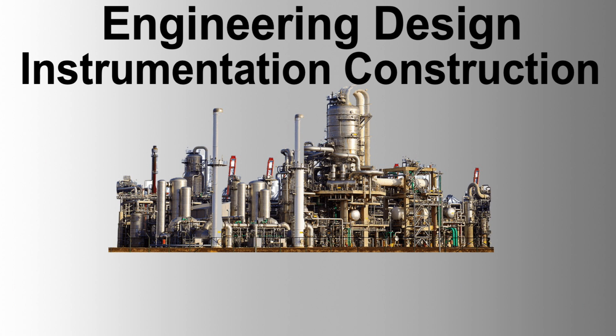Prefabricated consoles and system cabinets. Before prefabricated consoles and system cabinets are installed, a free space of sufficient size shall be allocated for unloading and unpacking. The access into the control room shall be free, i.e. not blocked by temporary or permanent structures. As much as possible before being uncrated, crates shall only be lifted at the indicated points. The slinging of crates using a running eye shall never be allowed, and spreaders shall be used where necessary to prevent the possibility of crushing the crate.